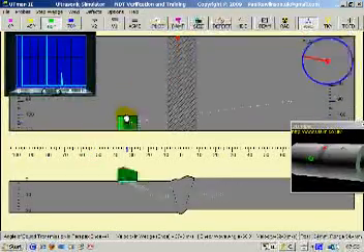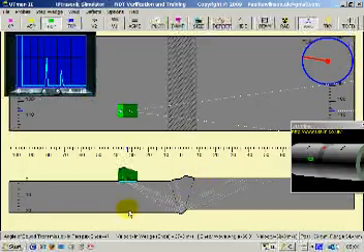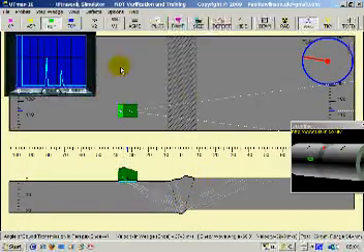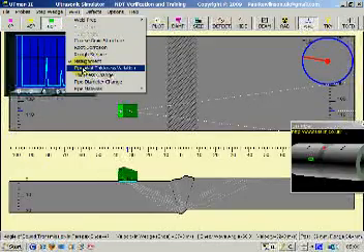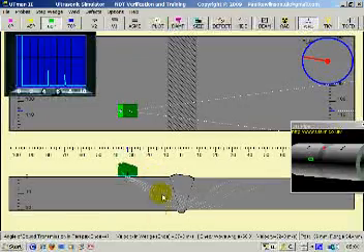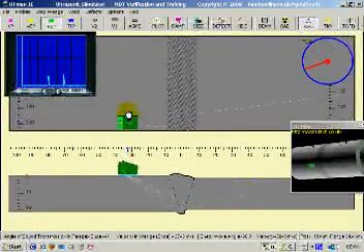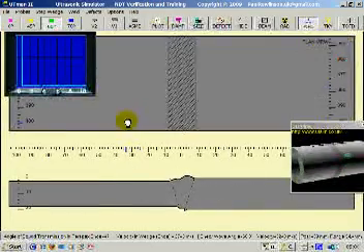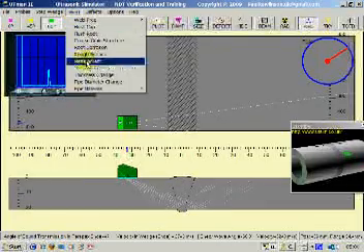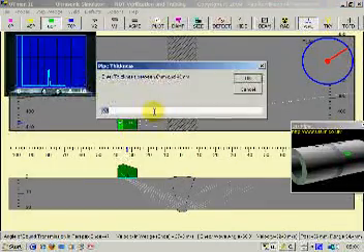We could have pipe misalignment. As you can see here, this pipe is higher than this side of the weld. Now, when misalignment is set, we can also pick pipe wall thickness variation. So, this side of the pipe is thicker than this side. We can change the thickness of the pipe.